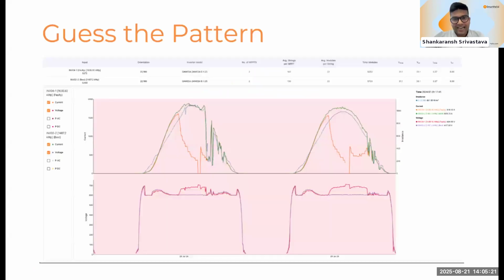I would explain this graph here. What you're seeing is the DC current and DC voltage coming from two inverters. One inverter is functioning okay. The other inverter, the current starts dropping and its voltage increases. The other inverter's voltage remains normal. So just looking at this pattern of current and voltage, you need to guess what the issue could be. Maybe if you could have the options up.